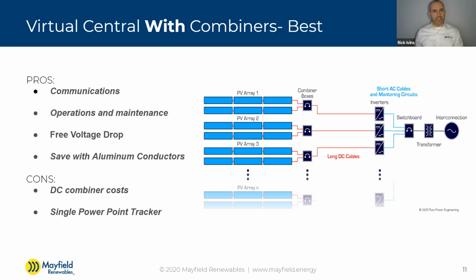So like I said, there's the technology equipment challenge to increasing voltage, but number one is really just the safety for the workers. And code does address that too, in a sense, where we can't do more than 1000. Well, 600 volts is our maximum voltage on residential one and two family dwellings. Then we go up to 1000 volts on all other buildings, and we're essentially capped at 1000 volts DC on buildings for our circuit conductors. So the 1500 volts really only comes into play on our ground mount systems, but for all the reasons why Rick was stating, we're effectively stuck there for a little while.